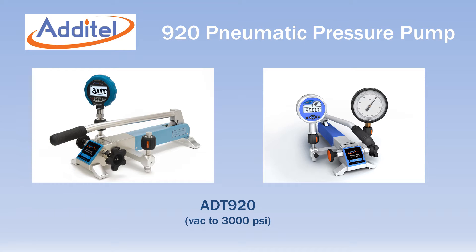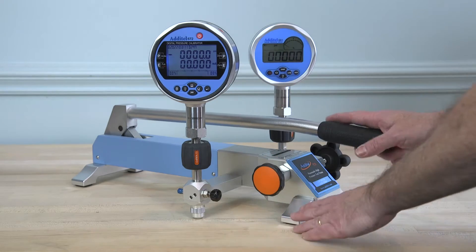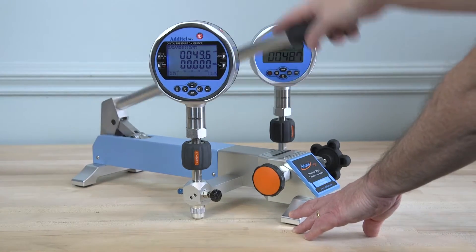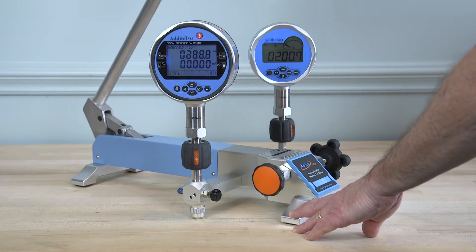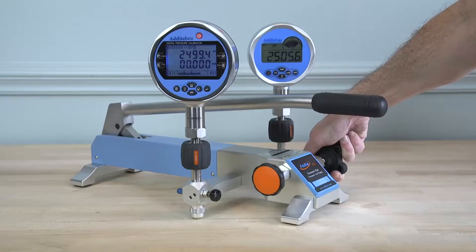The Additel ADT920 is a truly unique pneumatic pressure pump with a maximum range of 3000 PSI. The long handle allows rapid pressure generation to 3000 PSI in only 40 seconds, while a high quality screw press gives fine adjustment resolution as low as 1/1000th of a PSI.